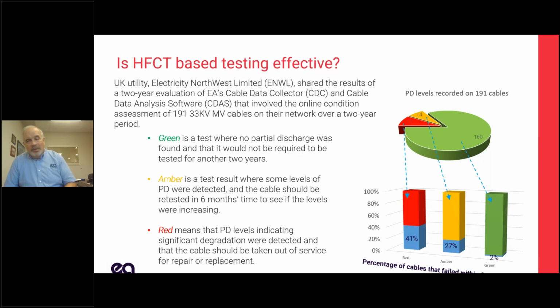Does it work? Well, we all want to know, does it work? Well, there's a utility in the UK. They tested 191 cables. Nice thing is they tested them, but they didn't replace them. They didn't repair them. And what they found was that 17% of their cables tested in the red, 14% in the yellow, and 160 of the cables, I'm sorry, not percentage, but cables, were in the green.